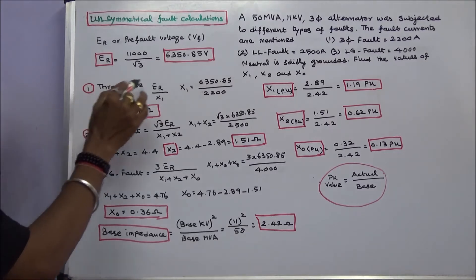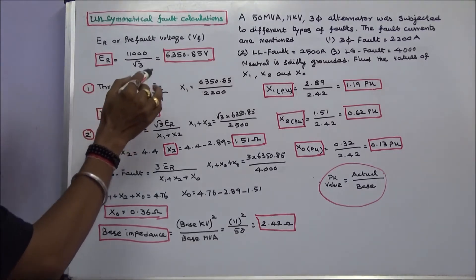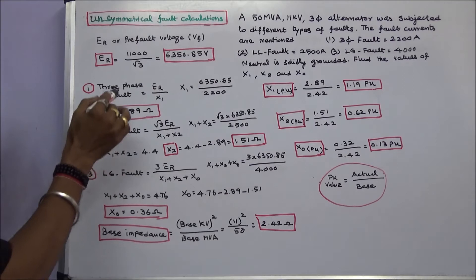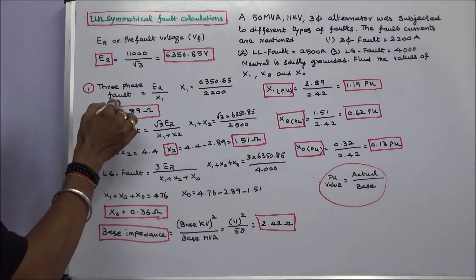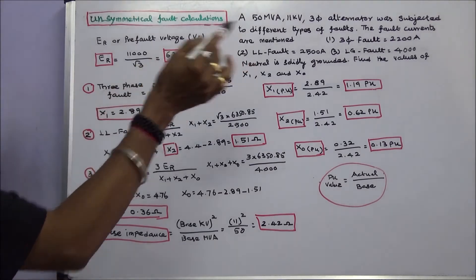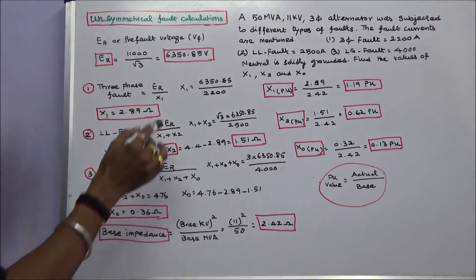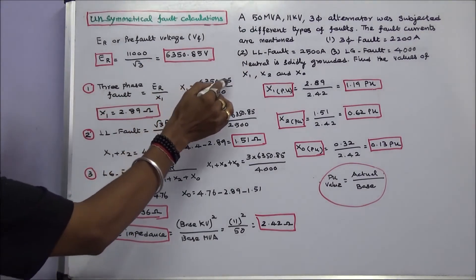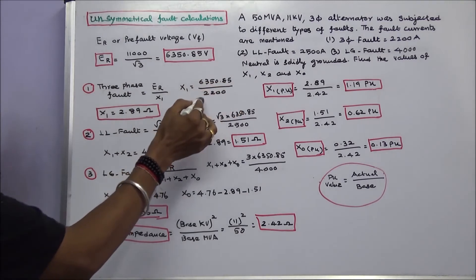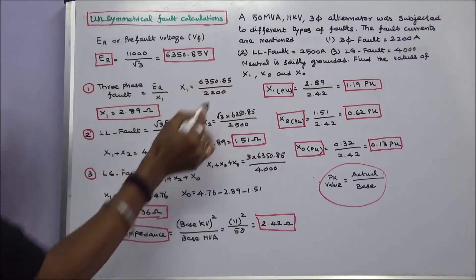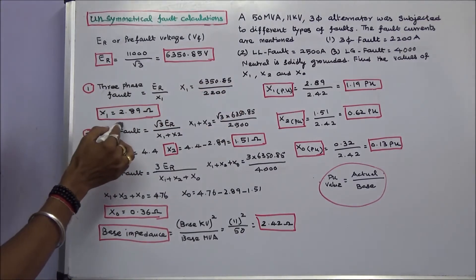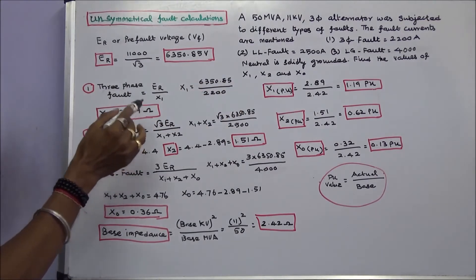For a 3-phase fault, the current equals ER divided by X1. This current is given as 2200 amps. Therefore X1 is equal to 6350.85 divided by 2200, giving X1 equal to 2.89 ohms.